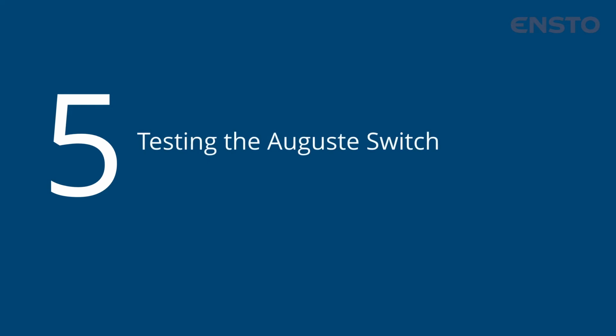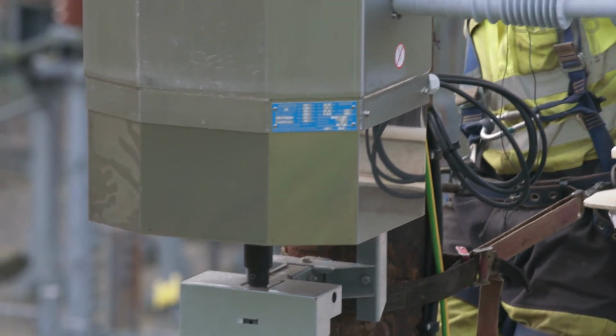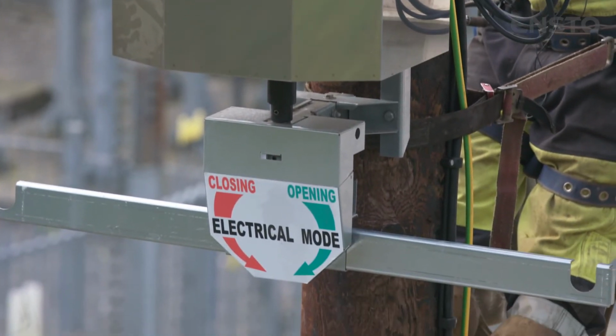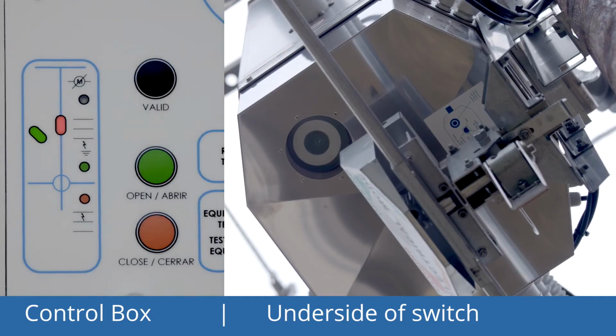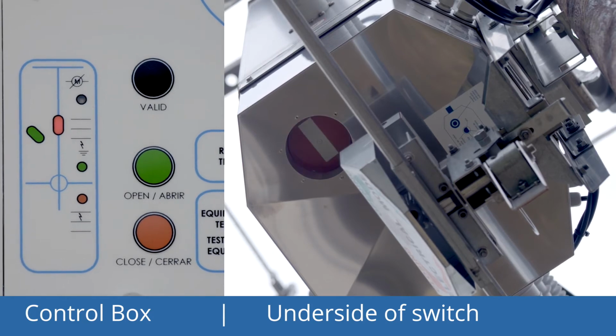Stage 5. Testing. Electrical testing. Before attempting to use the control box, ensure the manual operating arm is in the horizontal position to allow electrical operation. Press and hold together the valid and close buttons to close the switch.